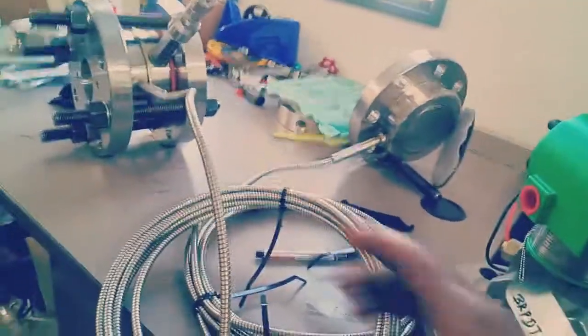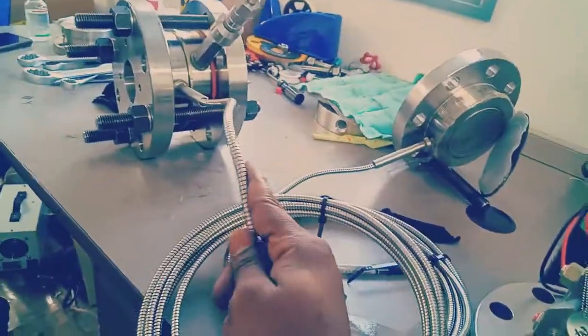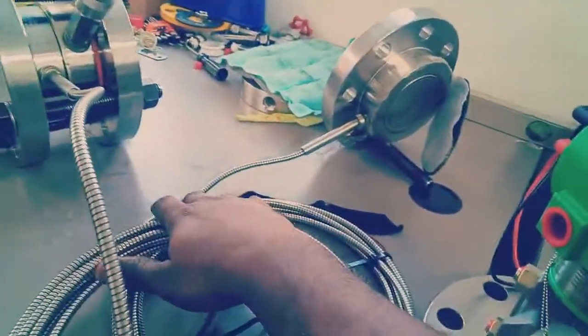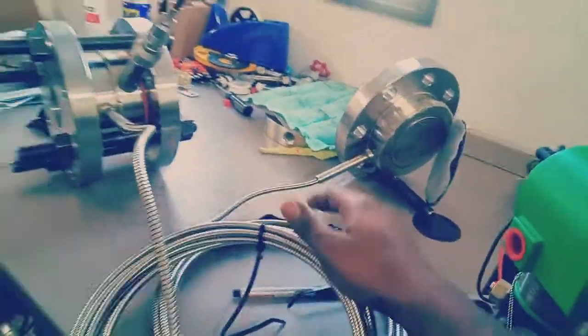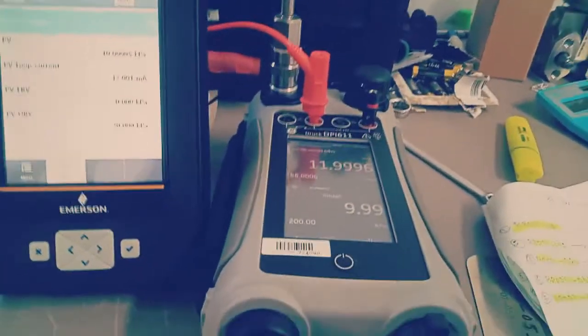You can see the transmitter connection here. This is the HP side, and that is LP side. LP side is open to atmosphere. HP side we connected to the pressure port, so by this way we're injecting the pressure.